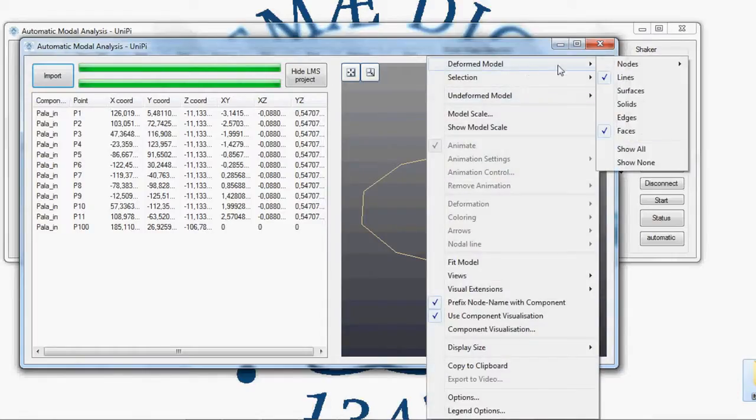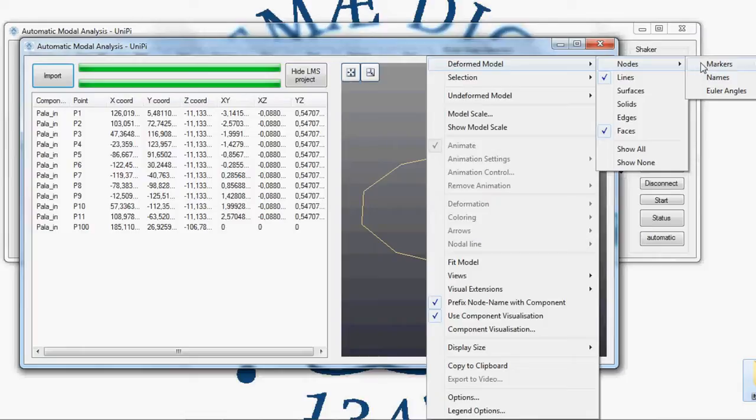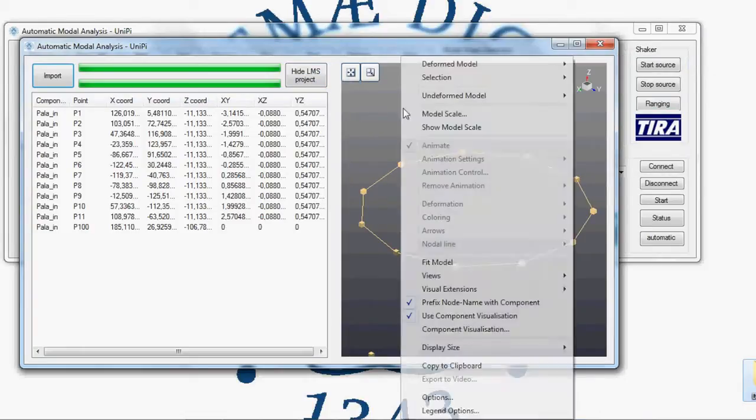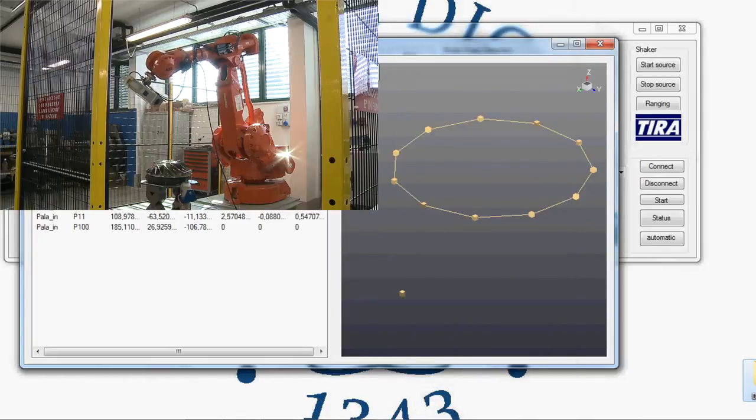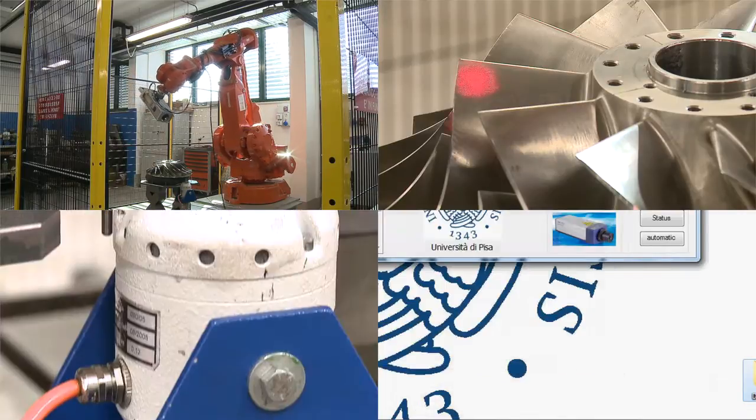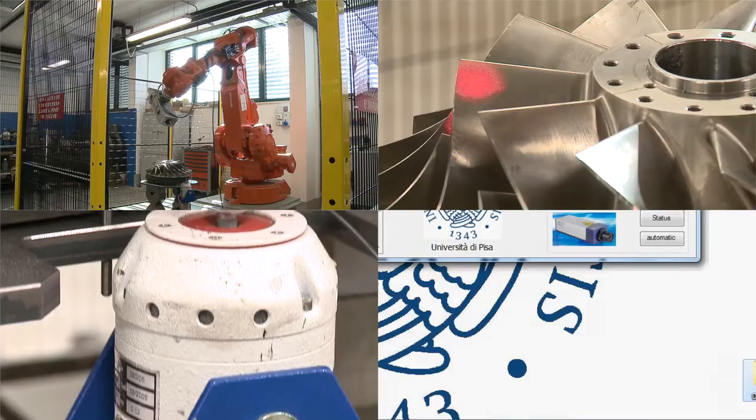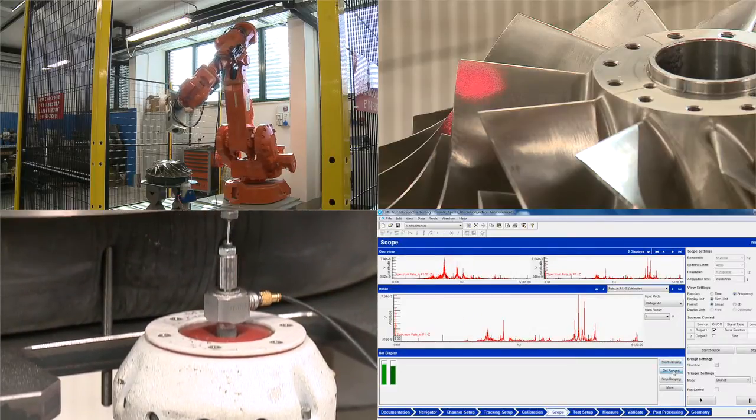A dedicated Visual Basic software manages all the components involved to complete the entire test in a short time. The measurement sequence is robot positioning, laser autofocus, excitation start, data acquisition.